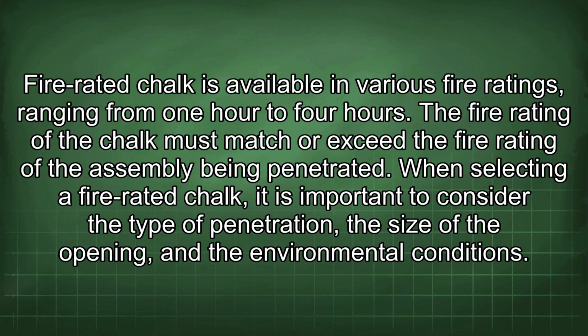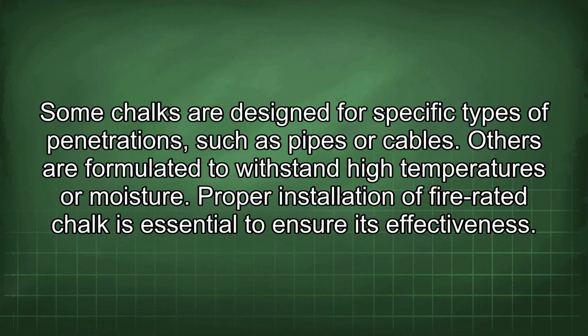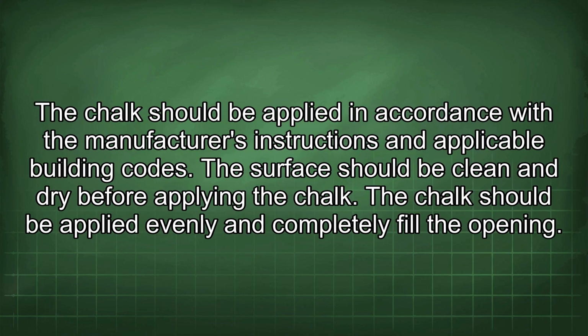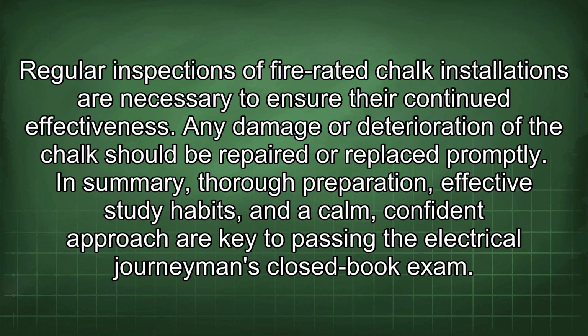When selecting a fire-rated caulk, it is important to consider the type of penetration, the size of the opening, and the environmental conditions. Some caulks are designed for specific types of penetrations, such as pipes or cables. Others are formulated to withstand high temperatures or moisture. Proper installation of fire-rated caulk is essential to ensure its effectiveness. The caulk should be applied in accordance with the manufacturer's instructions and applicable building codes. The surface should be clean and dry before applying the caulk. The caulk should be applied evenly and completely fill the opening. Regular inspections of fire-rated caulk installations are necessary to ensure their continued effectiveness. Any damage or deterioration of the caulk should be repaired or replaced promptly.